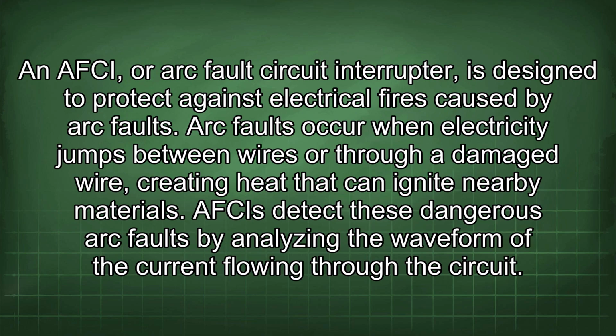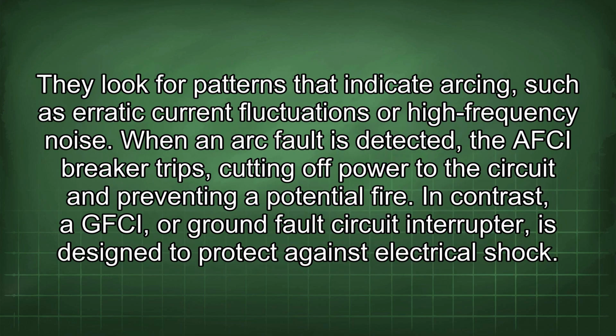An AFCI, or arc fault circuit interrupter, is designed to protect against electrical fires caused by arc faults. Arc faults occur when electricity jumps between wires or through a damaged wire, creating heat that can ignite nearby materials. AFCIs detect these dangerous arc faults by analyzing the waveform of the current flowing through the circuit. They look for patterns that indicate arcing, such as erratic current fluctuations or high-frequency noise.